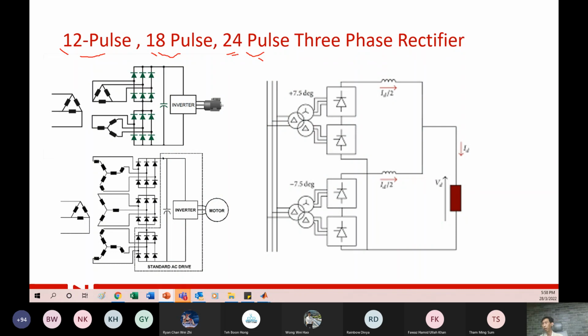What is the advantage of doing that? As we know, a rectifier will cause harmonic problems to the grid. The normal 6 pulse will create higher harmonics. So when you increase the number of thyristor switching, you indirectly reduce the harmonics. The higher the pulse number, the lower the harmonics. Even up to 24 pulse there are still harmonics, just not as high as with the 6. So it depends on your application. Do you need to further reduce the harmonics on the grid?